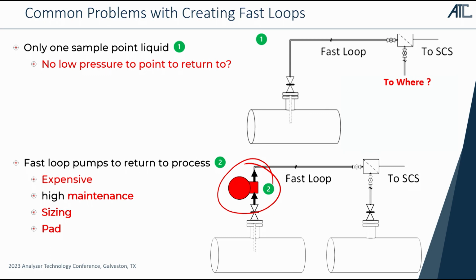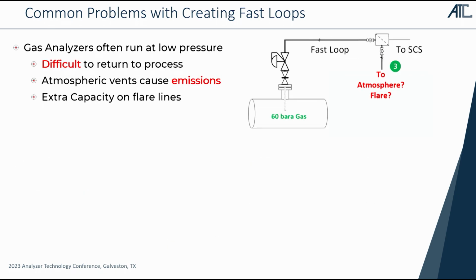But wait, there's more. If we're running gas, analyzers will often run at low pressures. If we look at something like our gas chromatographs or an online UV-vis spectrometer, they'll often be running near ambient pressures. And if our sample gas is at high pressures, say a natural gas pipeline, I can't return process fluid back to the high pressure spot very easily. It's tough pumping the gas back up to, say, 60 bar if I'm sampling from a high pressure natural gas pipeline. So it can be difficult to return to process.